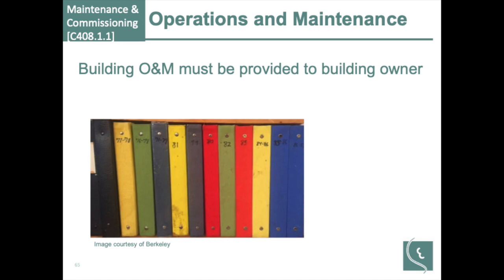So it's not a great enforcement mechanism, but at least the code is recognizing this is important, because if we aren't able to maintain a building, then all our bells and whistles are going to be gone. And it is not uncommon to see the newer a building is, the more energy it uses per square foot, which is backwards from what the model codes are telling us should be happening. And a lot of that goes back to we're not able to maintain these. We try to fix stuff by putting more gizmos and gadgets in rather than fixing the problem to start with.